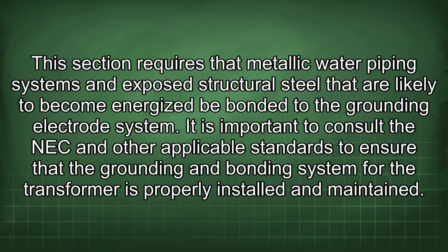This section requires that metallic water piping systems and exposed structural steel that are likely to become energized be bonded to the grounding electrode system. It is important to consult the NEC and other applicable standards to ensure that the grounding and bonding system for the transformer is properly installed and maintained.